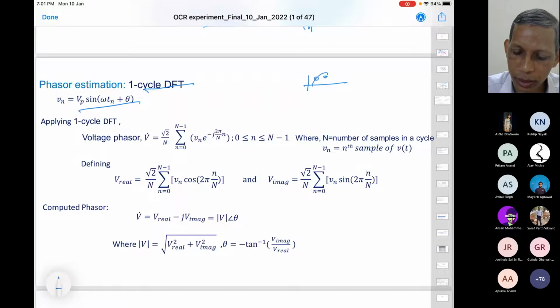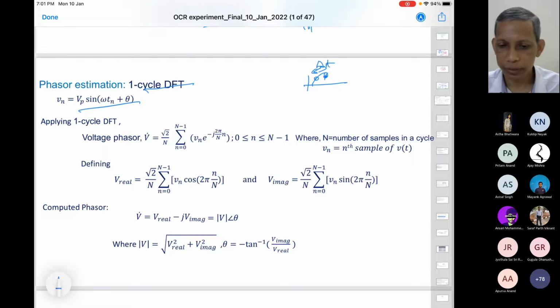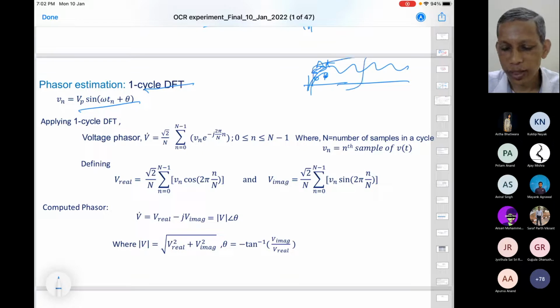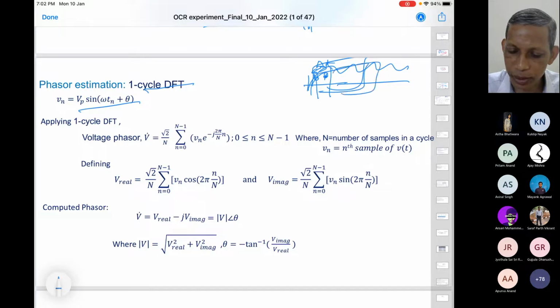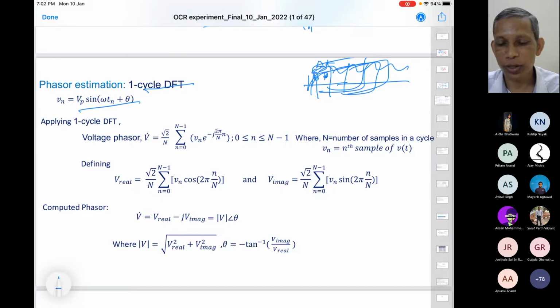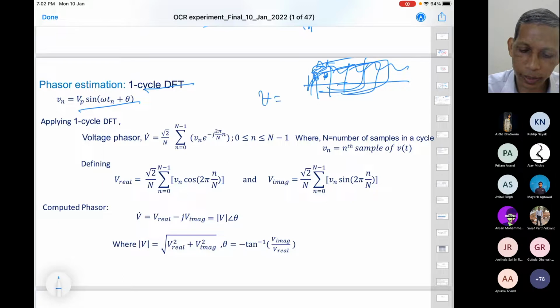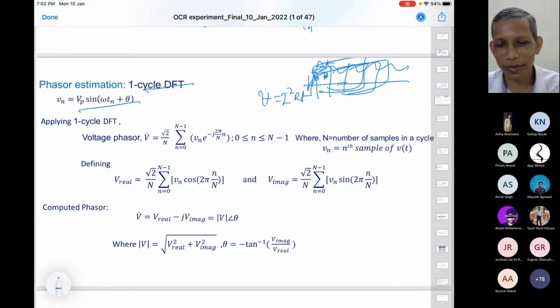Suppose we have a signal like this. This is delta t, the intersampling interval. If the sampling rate is high, delta t will be small. Let us say the fault is progressing. We will not wait one cycle, two cycles, or three cycles to make a decision. Our window goes on shifting, every sample, because it is a protection decision. The quicker you can make the decision and trip the circuit breaker, the safer it will be. Agree? Otherwise the same I square RT heating will go on. If you allow more time, it will damage.